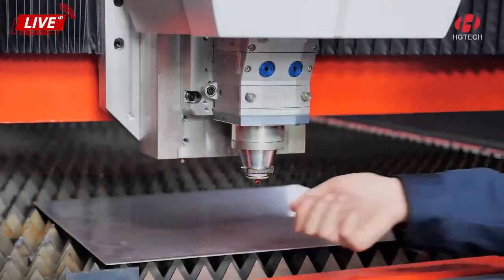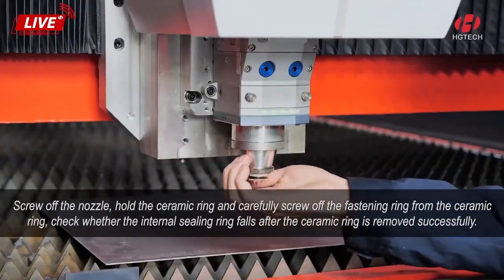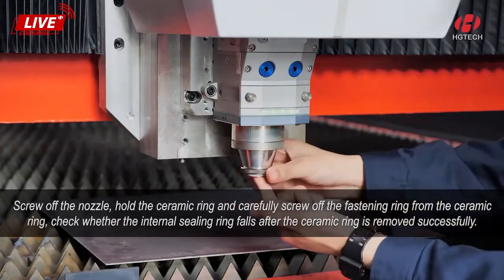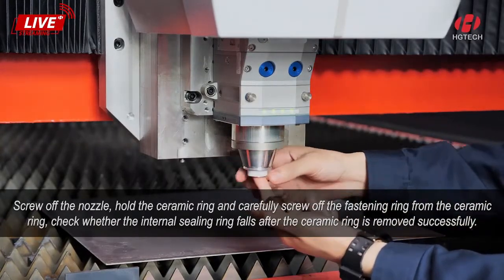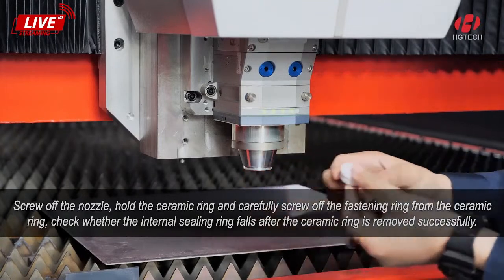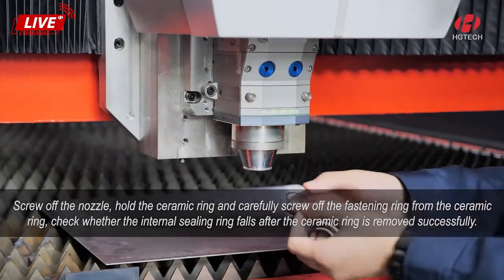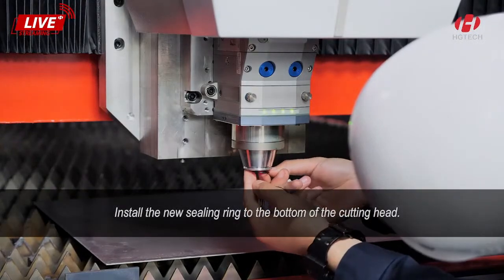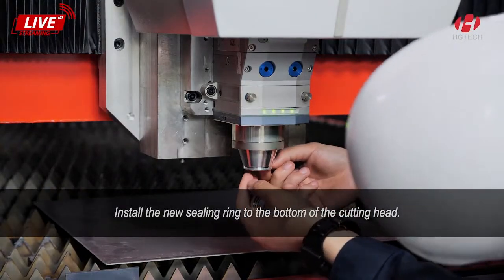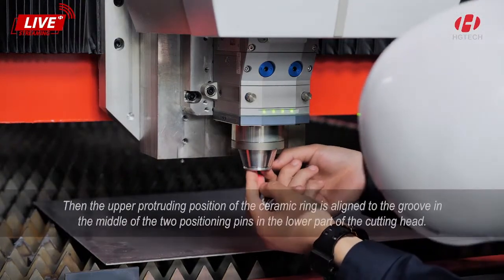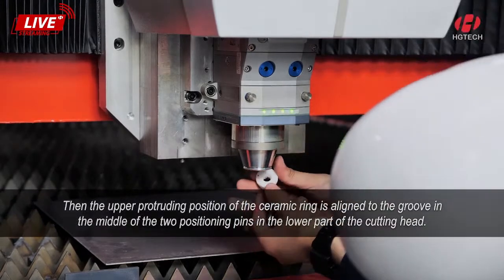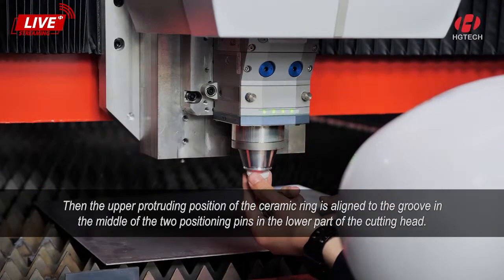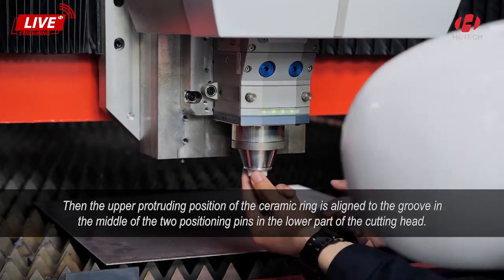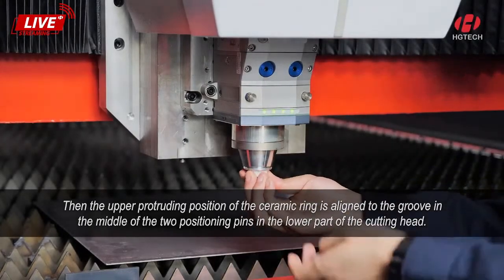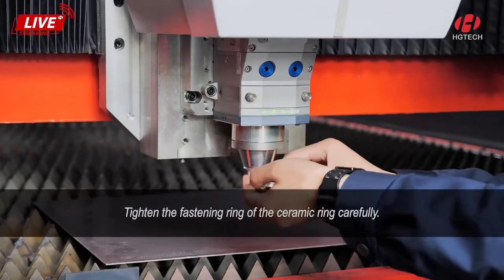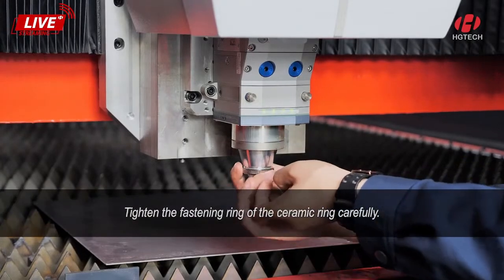Screw off the nozzle, hold the ceramic rings and carefully screw off the fastening ring from the ceramic ring. Check whether the internal sealing ring falls after the ceramic ring is removed successfully. Install the new sealing rings to the bottom of the cutting head. Then align the upper protruding position of the ceramic ring to the groove in the middle of the 2 position pins in the lower part of the cutting head. Tighten the fastening ring of the ceramic ring carefully.